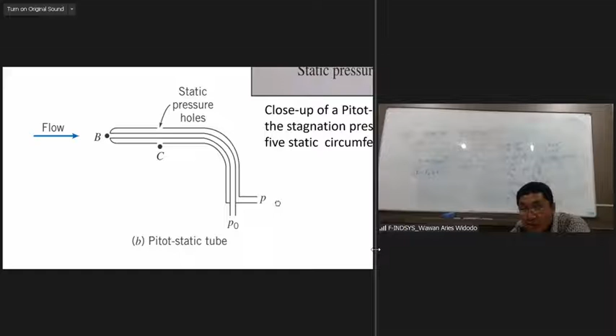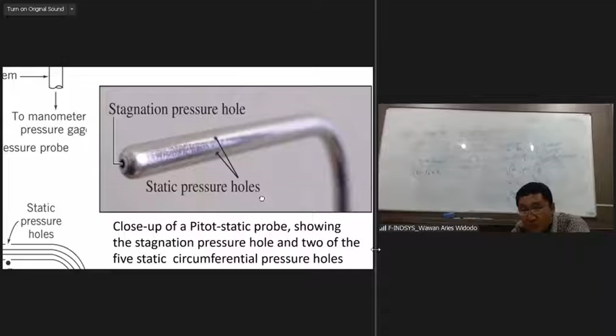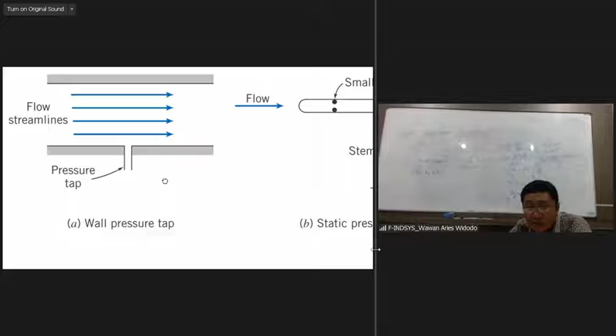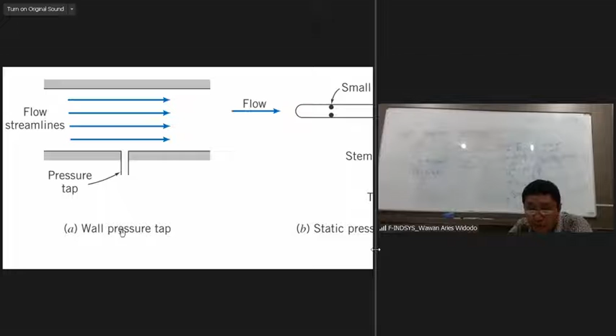So you can see from this picture, the air will be flowing into the small hole here, and this measures the stagnation pressure. This hole is connected here, and this P indicates the static pressure. Actually, this one measures stagnation pressure, and these two holes here measure static pressure. So this is the principle of how to measure flow along streamlines. This is a pressure tap. Actually, from the wall pressure tap we can measure the static pressure.